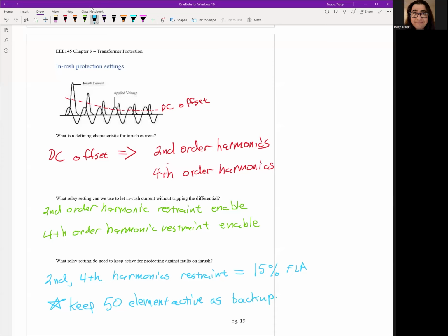You should never ever run a transformer naked with no protection at all, because you're gambling on a $3 million device. So don't ever do that. That's how you protect against inrush: detect inrush by the second or fourth order harmonic, and restrain it so we can let the transformer energize and have the 50 element active as a backup.